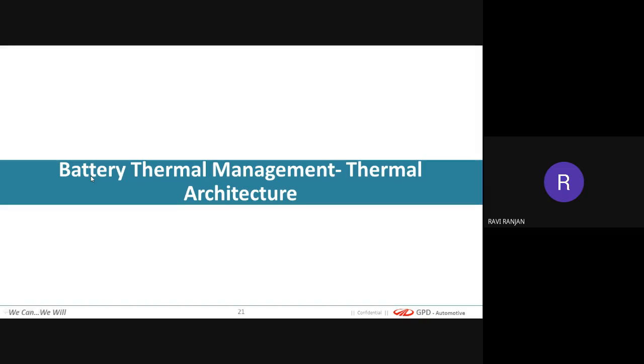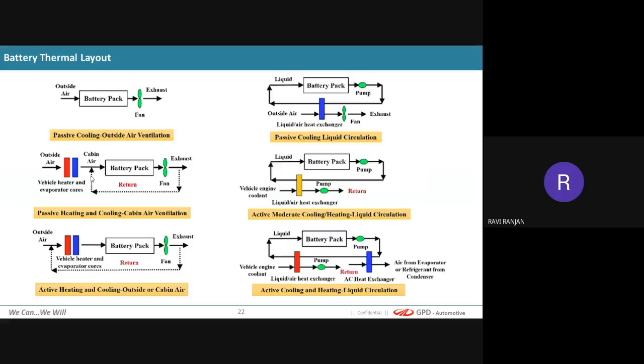Now coming to battery pack thermal management. The temperature requirement is close to 15 to 35 degrees Celsius, but we operate from minus 10 degrees to 50 degrees Celsius. So we have to go for additional thermal management - either providing a heater for low ambient conditions, or a refrigerant cooling system for high ambient conditions. Only then will we achieve the requirement of the boundary condition.